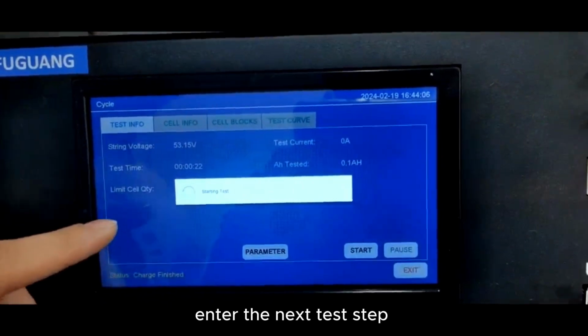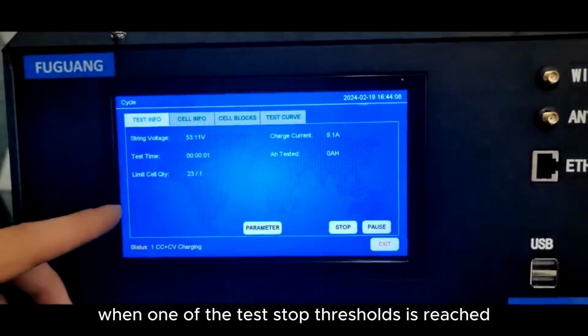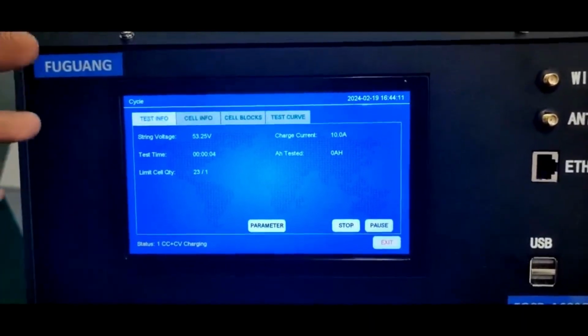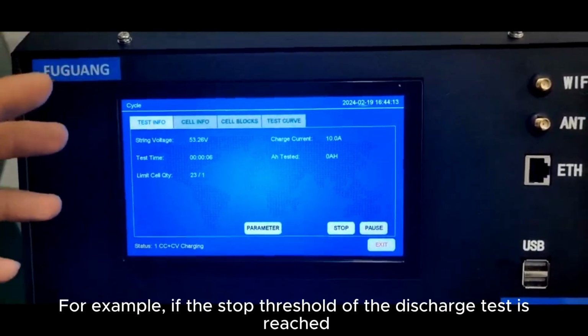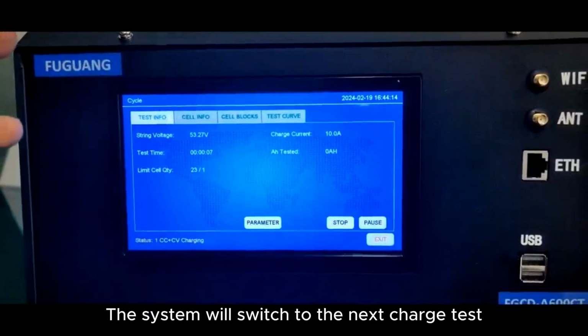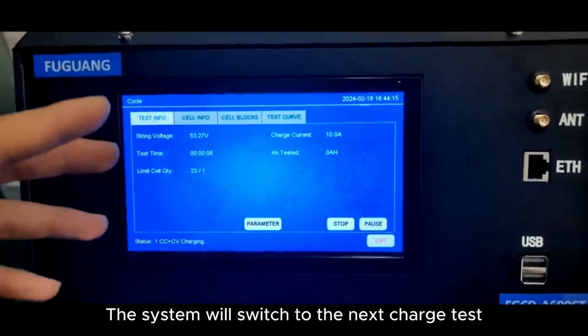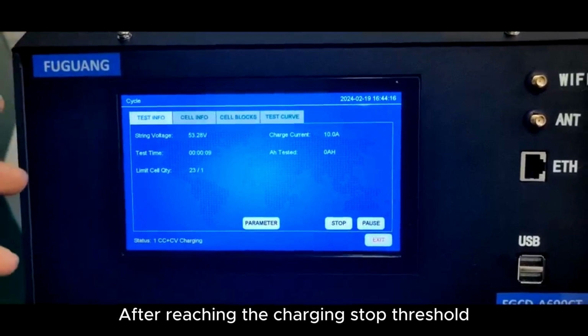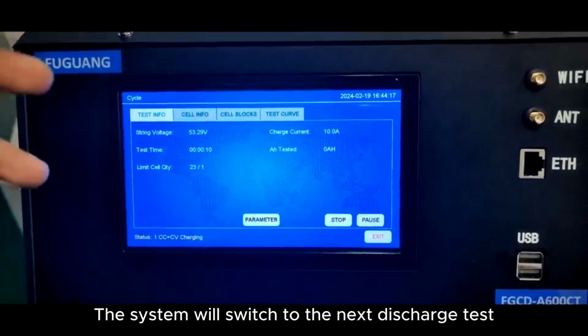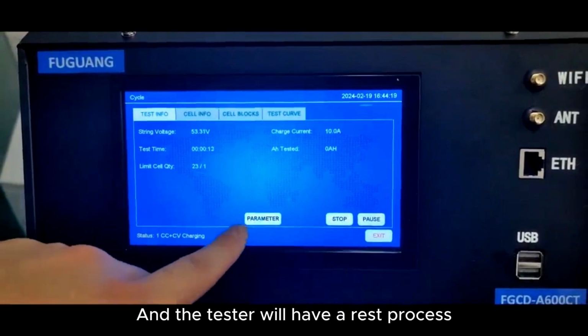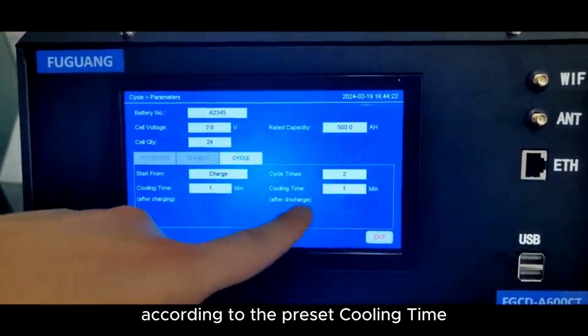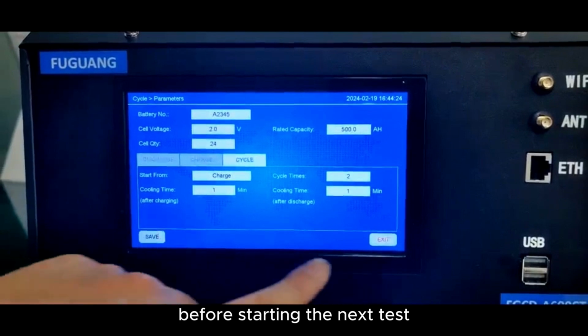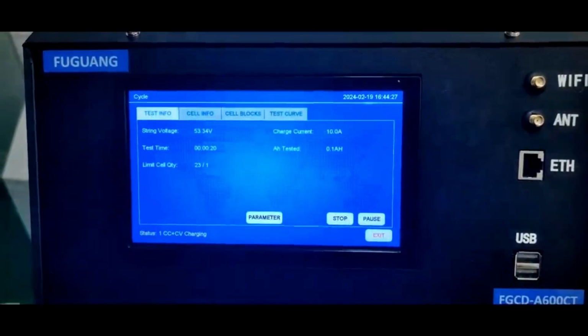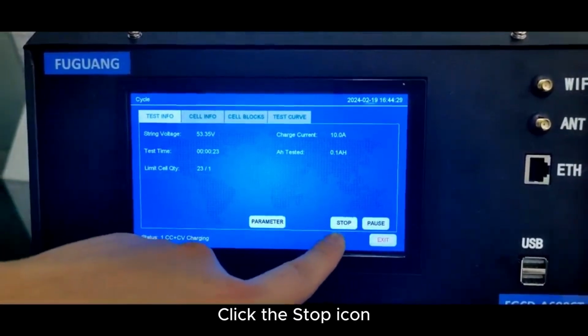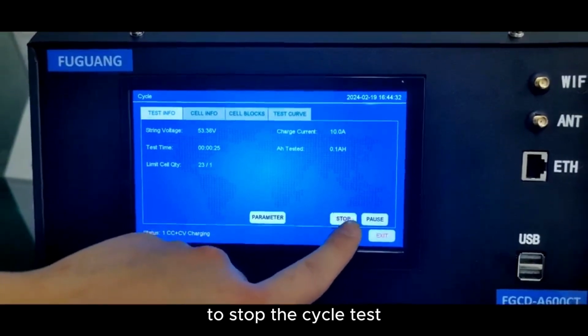During the test, the system will automatically enter the next test step when one of the test stop thresholds is reached. For example, if the stop threshold of the discharge test is reached, the system will switch to the next charge test. After reaching the charging stop threshold, the system will switch to the next discharge test, and the tester will have a rest process according to the preset cooling time before starting the next test. Click the stop icon to stop the cycle test.